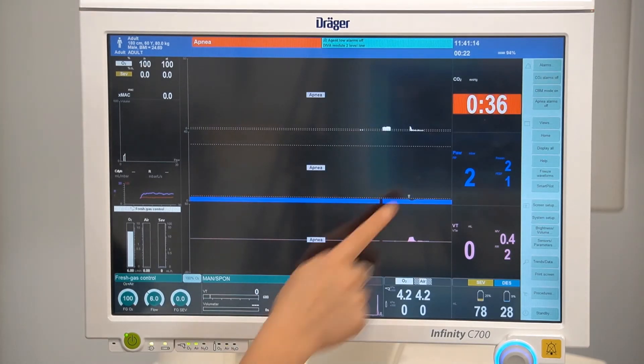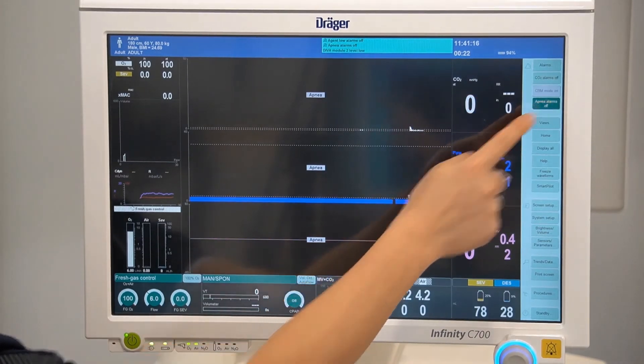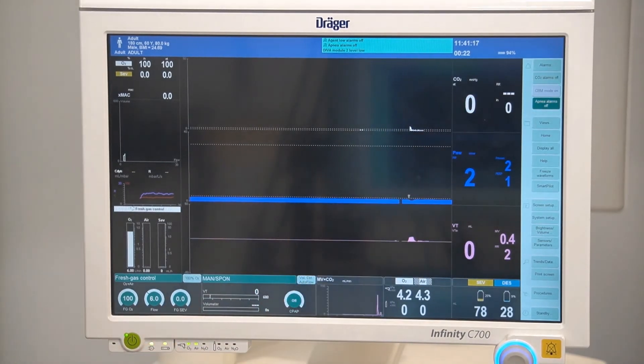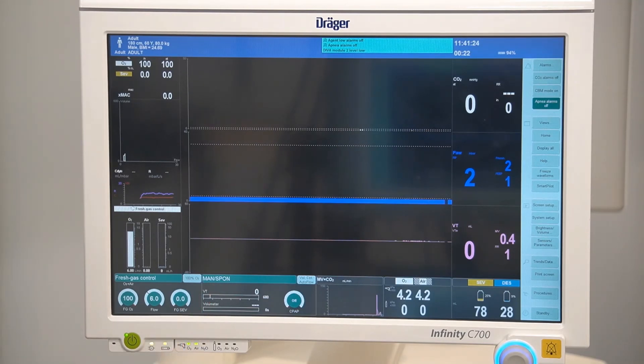Apnea alarms off suppresses apnea and minute ventilation low alarms during manual spontaneous phase. When changing to mechanical ventilation, the alarm system will become active again.